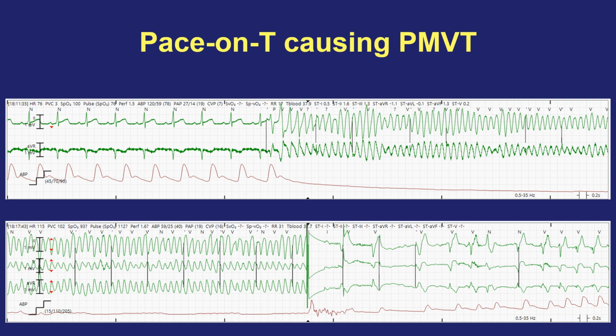Here's another example where the sensitivity in this patient was set at a level that was too high a number, too insensitive. This was not asynchronous pacing. You can see there isn't pacing occurring throughout this time. It's appropriately sensing QRS complexes, but just barely so, because the pacemaker box missed the fact that there was a QRS complex here, and it paced right after, thinking there was no heartbeat. And unfortunately, that pacing spike in the ventricle occurred on a T wave, and it caused polymorphic VT to occur.